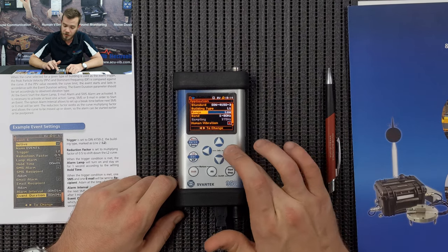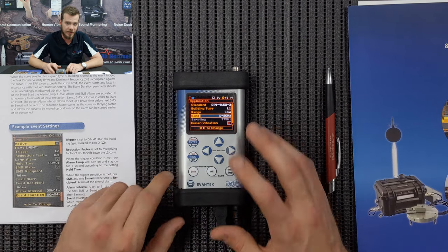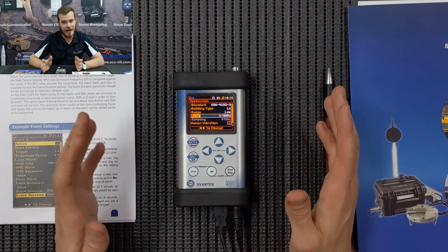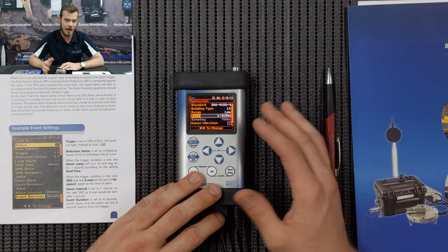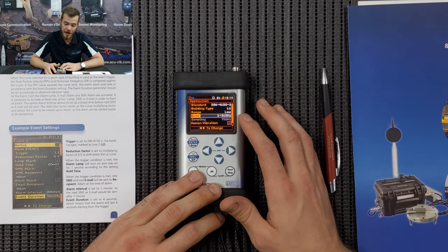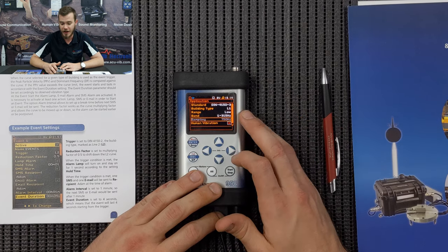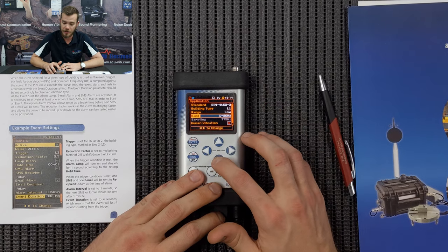We also have an option for a range, a high or a low range, and we have a frequency band is what we're trying to look at. Typically, default 1 to 80 hertz should be fine for low frequency vibrations. If you are experiencing something larger than that, then use a higher band sampling, 1 to 315 hertz. The sampling rate can't be changed, these are predefined. I'm going to leave it on 1 to 80 hertz for now.